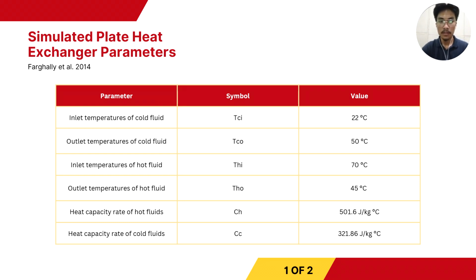So the data presented here are based from the study of Farghally and others in 2014, wherein one of their methodology includes a simulated plate heat exchanger. However, they did not specify the specific type of plate heat exchanger in this one, but we still use this table on our technical report because it contains the specific parameter and important variables that are helpful in the design and operation of a welded plate heat exchanger.